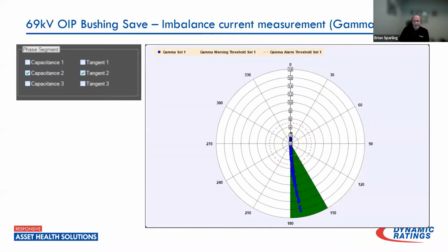Now, to understand this, when looking at the monitor, this is what one could see as a result of alarms coming from a bushing monitor. And if given the software provided by the vendor, you're able to see this data in terms of a polar plot and also trending. In this case, each blue dot you see in that polar plot is representative of a measurement made over time. And so there's a whole bunch of measurements being made here, but it's pointing in this case at a significant capacitance change in the bushing. This software helps us understand this capacitance change and which phase is having the issue.